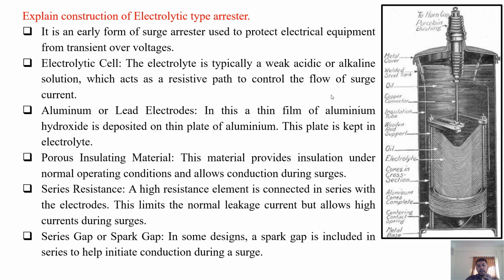So the electrolyte is typically a weak acidic or alkaline solution which acts as a resistive path to control the flow of surge current. Aluminum or lead electrode like this is the main electrode. So in this, a thin film of aluminum hydroxide is deposited on a thin plate of aluminum. This plate is kept in the electrolyte.